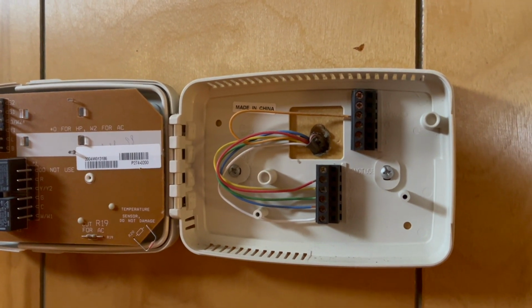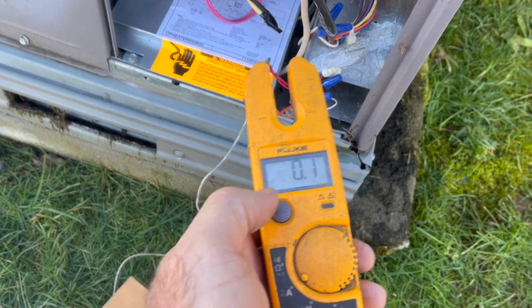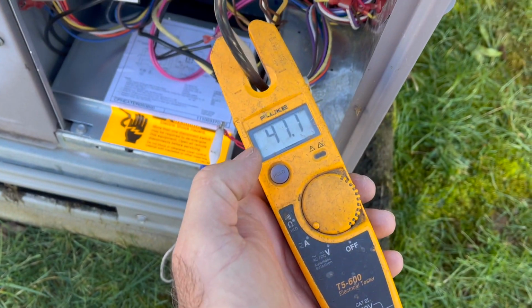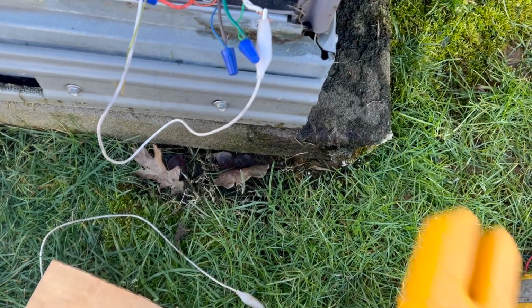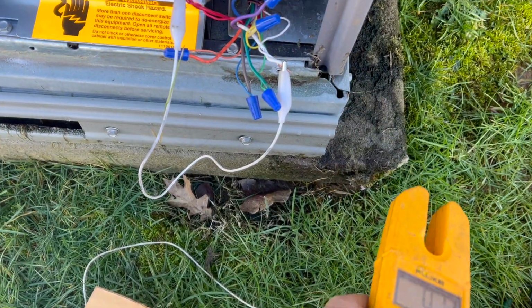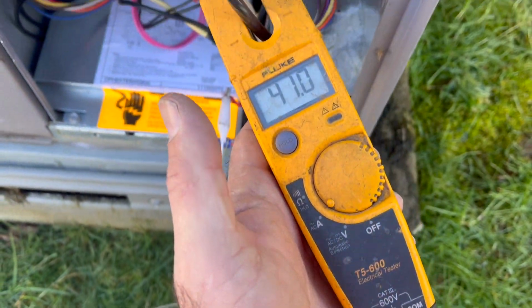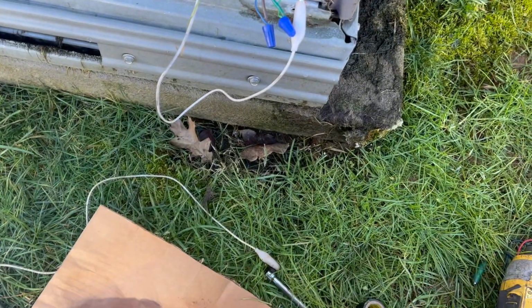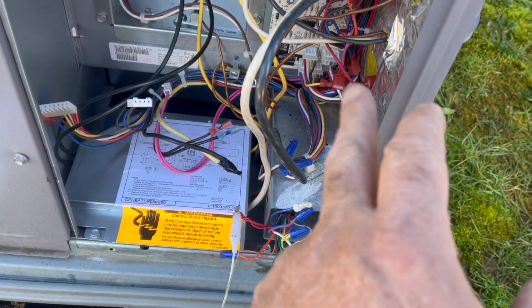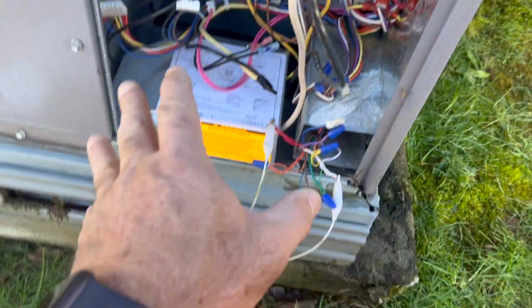so she don't have the additional cost of a thermostat on this deal. Although there's no reason why it shouldn't work, just thought I might go ahead and check the electric heat before I leave, and all I've done is hook the red to the white there. So it's working fine. It's got the blower on. The only other thing, we've got that board replaced. We've replaced the contactor. It apparently didn't hurt the fan motor because it's running.